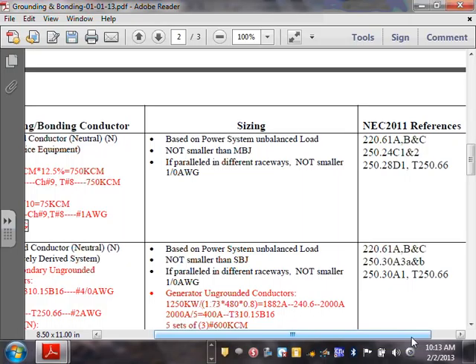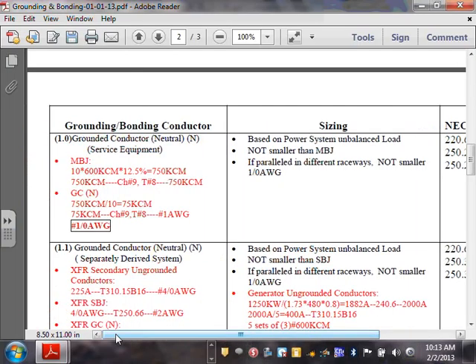So everybody kind of going to give me a pass on these. You're not going to go check it now at least. Okay, so then this is how we size it. So let's go size it. When we size, guys, the grounding conductor, I decided single-handedly, Chad, to run, instead of 11 runs here, 10 runs of 600 kcm. Can I do that? 10 instead of 11. Remember I said 11, 500. I can run 10, 600. If you do the math on how much amp, you can carry a switchgear 4000 amp with 10 runs of 600 kcm.